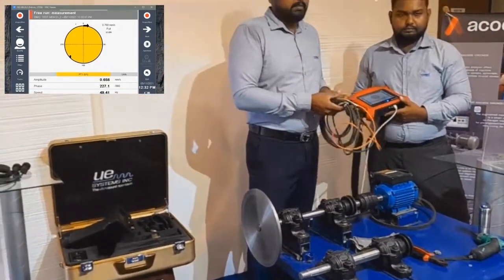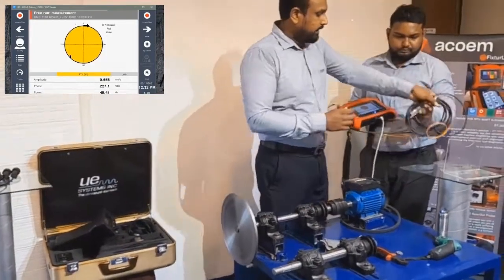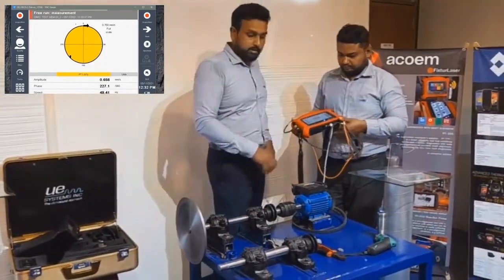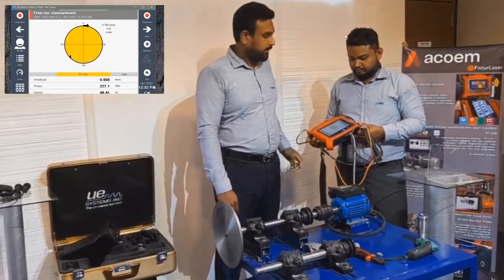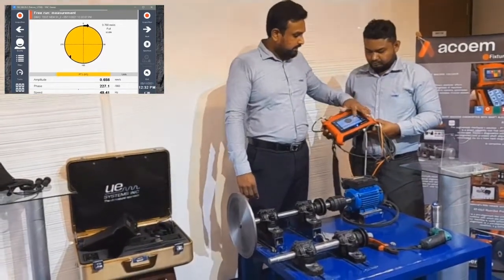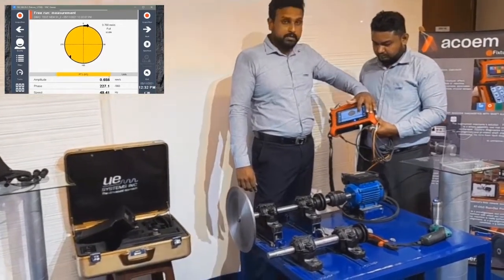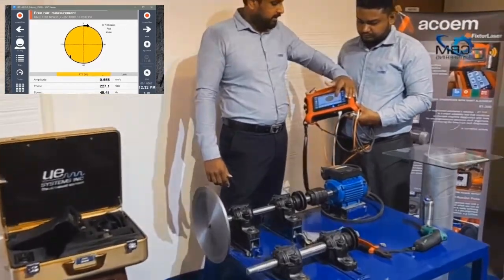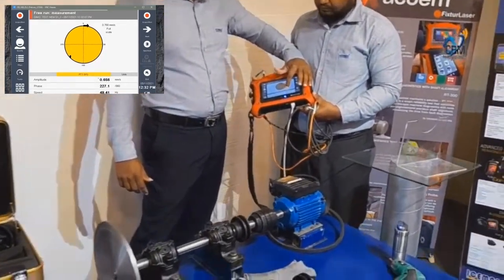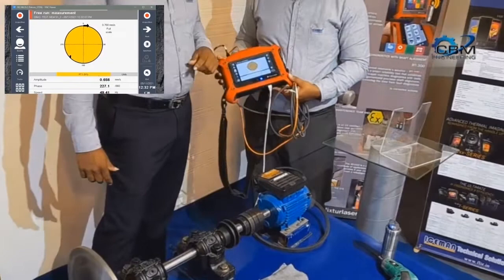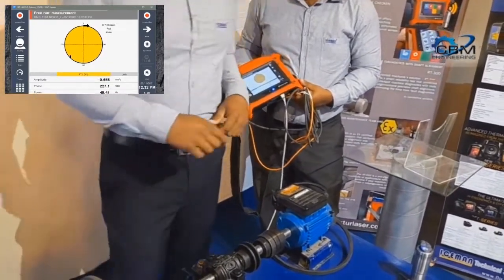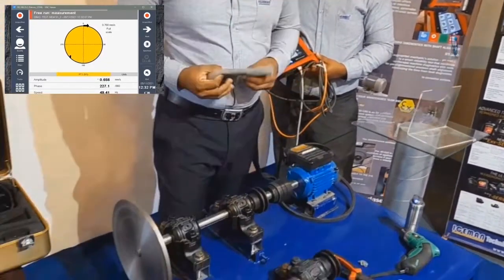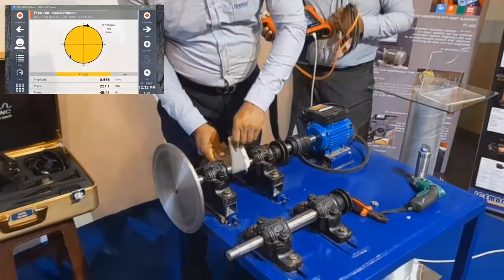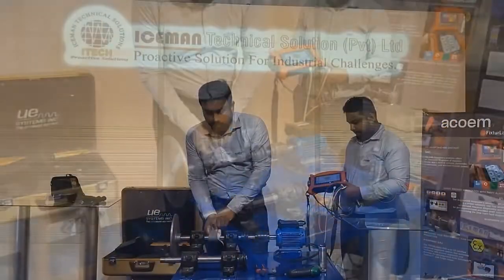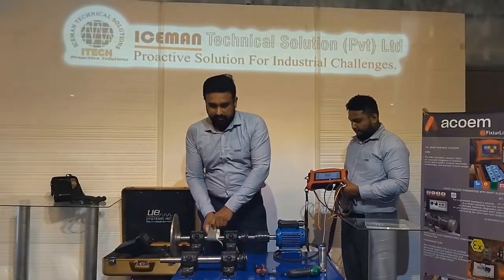We have already taken the vibration measurement. We will see what the value of this vibration amplitude is. There is a very high vibration value due to the imbalance, that is 0.658 amplitude. So now we are going to add the trial weight. Trial weight means a known weight and a known angle.